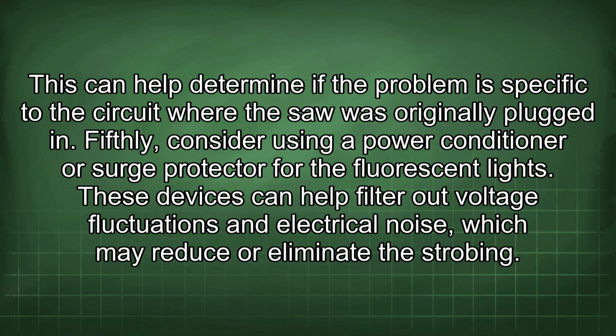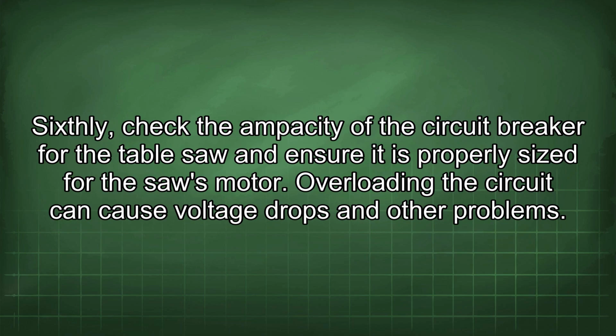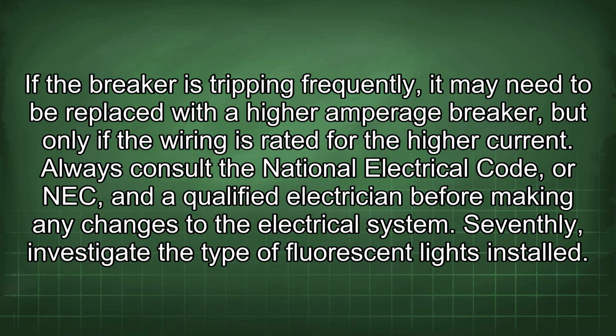Fifthly, consider using a power conditioner or surge protector for the fluorescent lights. These devices can help filter out voltage fluctuations and electrical noise, which may reduce or eliminate the strobing. Sixthly, check the ampacity of the circuit breaker for the table saw and ensure it is properly sized for the saw's motor. Overloading the circuit can cause voltage drops and other problems. If the breaker is tripping frequently, it may need to be replaced with a higher amperage breaker, but only if the wiring is rated for the higher current. Always consult the National Electrical Code, or NEC, and a qualified electrician before making any changes to the electrical system.